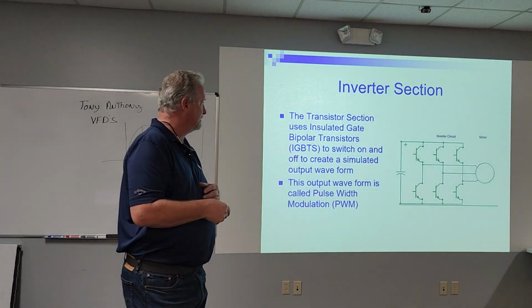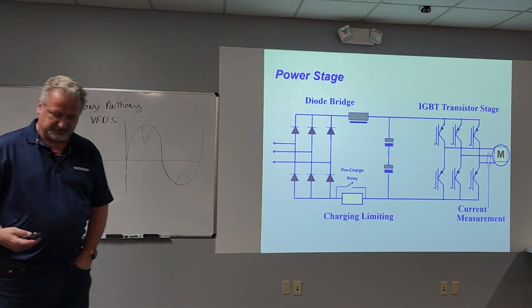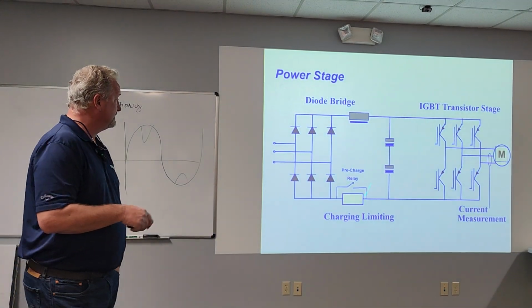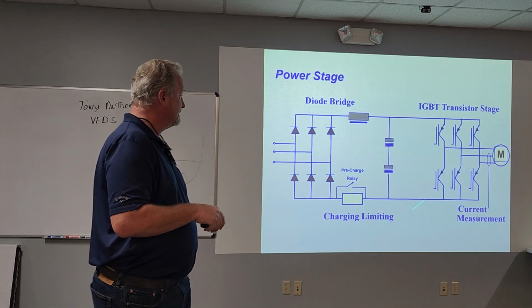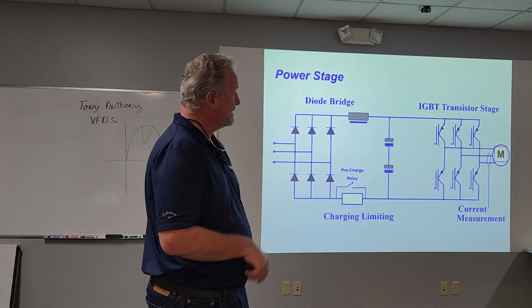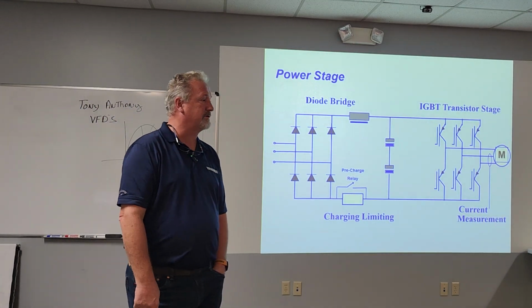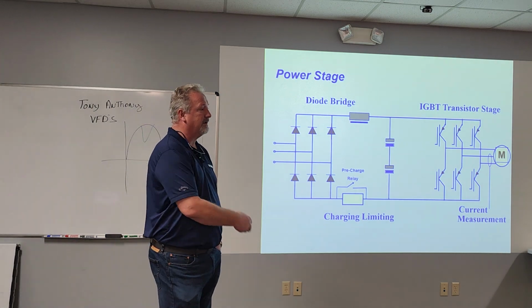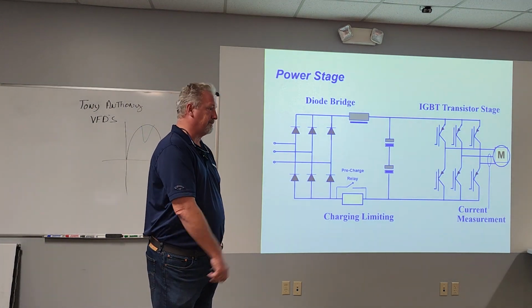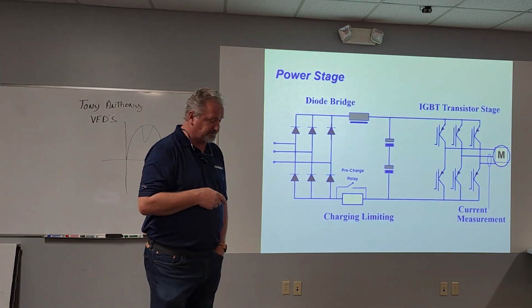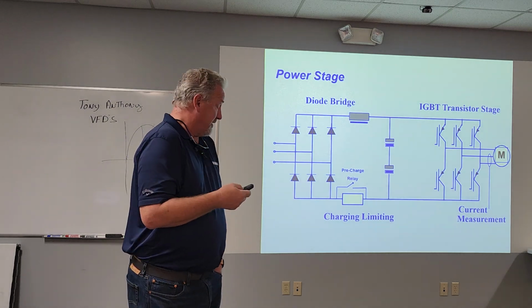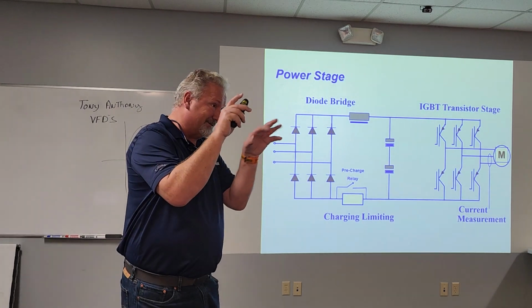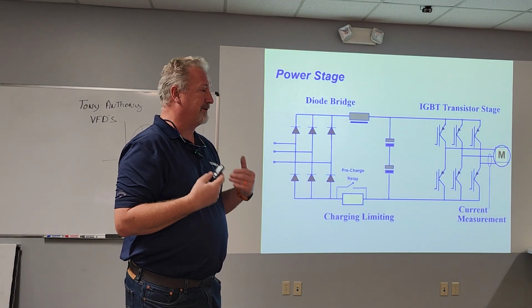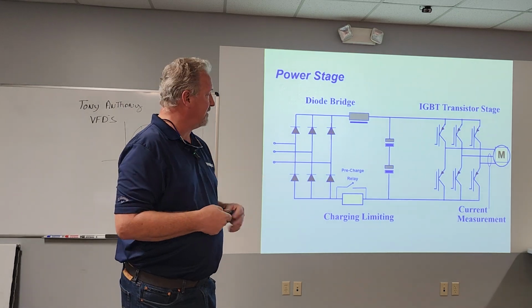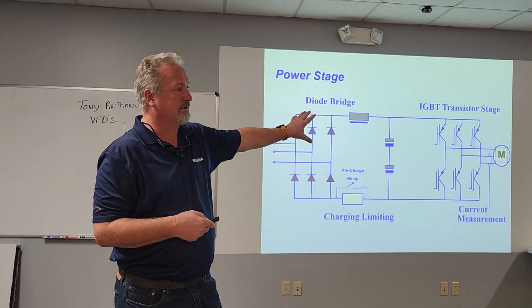So that's the drive. Let's go back real quick. Really, that's all there is to a drive. Got the diode bridge, the DC bus, and a bunch of IGBTs we fire to create that pulse width modulation to change the speed and voltage on the motor, to control the motor. So that's all there is to it. Now, obviously, there are some controls in there that we can do and do different things, which is beyond what we're doing here, but this is basically how every drive out there works.